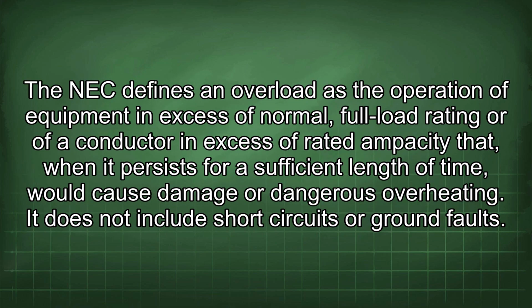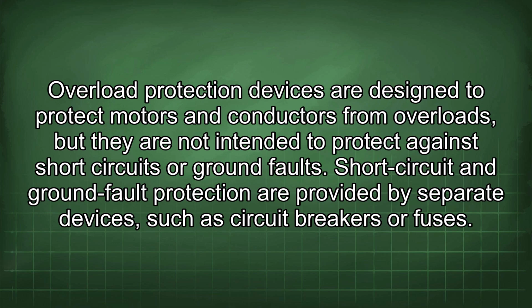The NEC defines an overload as the operation of equipment in excess of normal, full load rating, or of a conductor in excess of rated ampacity that, when it persists for a sufficient length of time, would cause damage or dangerous overheating. It does not include short circuits or ground faults. Overload protection devices are designed to protect motors and conductors from overloads, but they are not intended to protect against short circuits or ground faults. Short circuit and ground fault protection are provided by separate devices, such as circuit breakers or fuses.